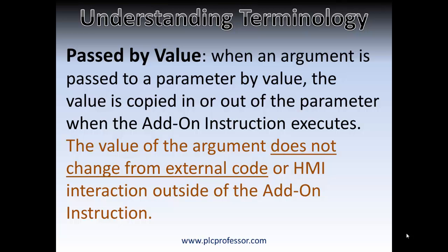Pass by value means when an argument is passed to a parameter by value, the value is copied in or out of the parameter when the add-on instruction executes. Therefore the value of the argument does not change from external code or HMI interaction outside of the add-on instruction. You may have to review this several times before you get it firmly in mind. In one case you're bringing in a value from a tag — that value is not going to change because you're not referring to the tag again. Whereas when you're referencing a tag, every time you use that argument, its value is out in the general population where it can be changed by any other code in the controller.